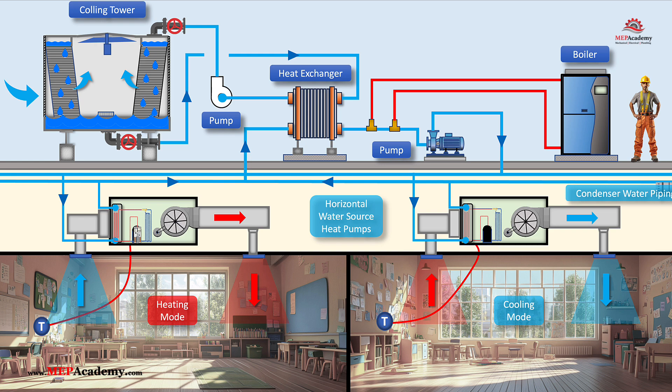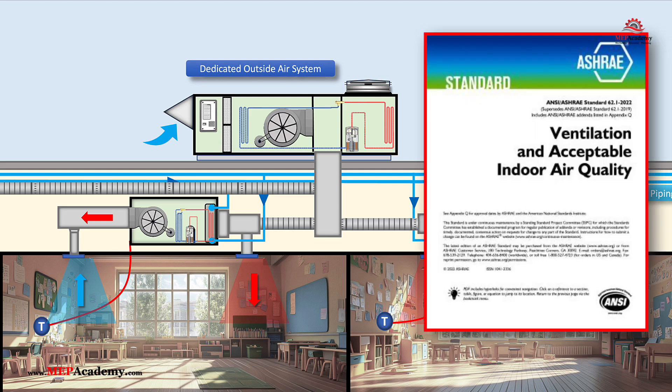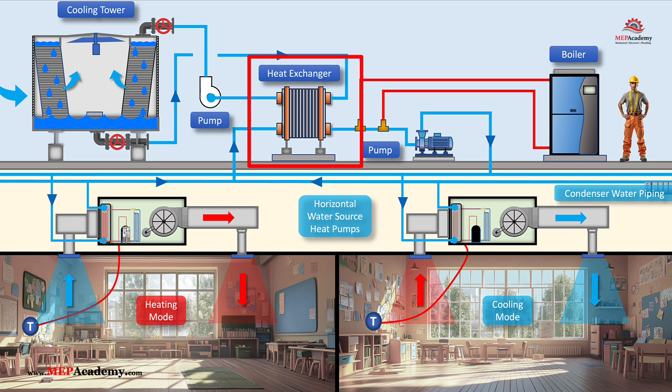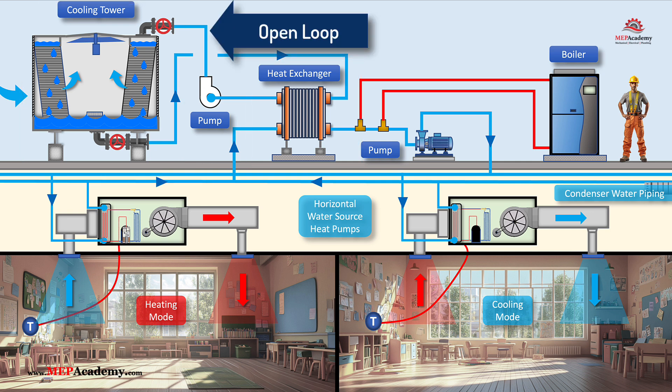To comply with building codes and provide fresh air, many water source heat pump systems incorporate a dedicated outside air system. This unit provides ventilation air that is conditioned independently of the water source heat pumps, improving indoor air quality and ensuring compliance with ASHRAE standards. A plate and frame heat exchanger is a critical component in water source heat pump systems when utilizing an open loop cooling tower. It is installed between the open loop cooling tower and the closed loop water source heat pumps, effectively creating two separate water loops.